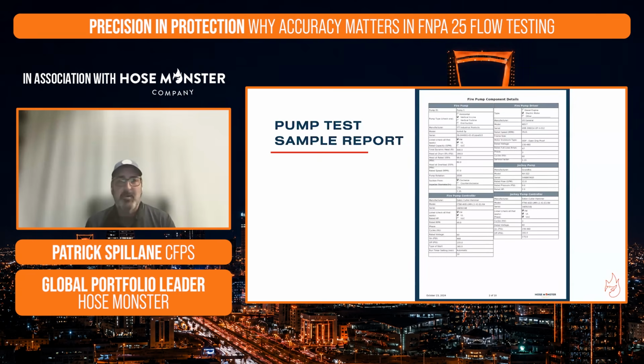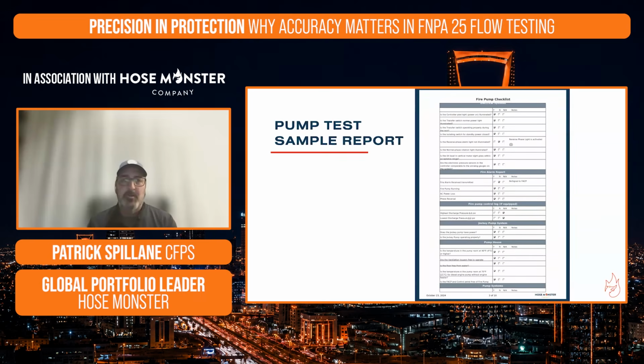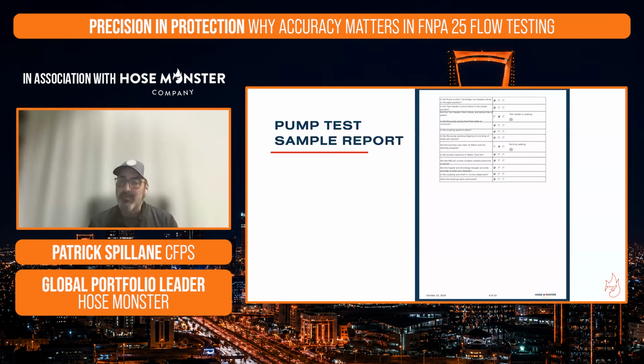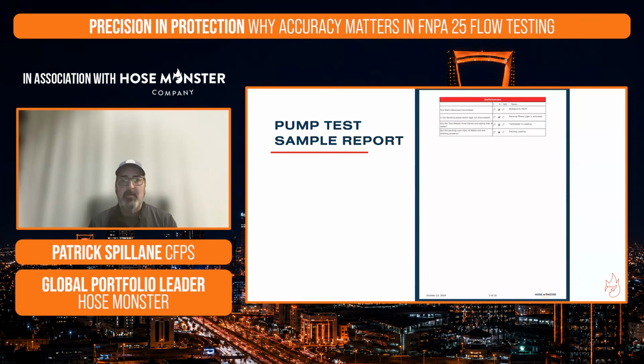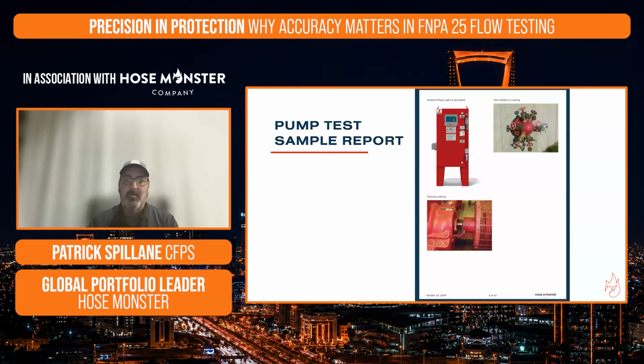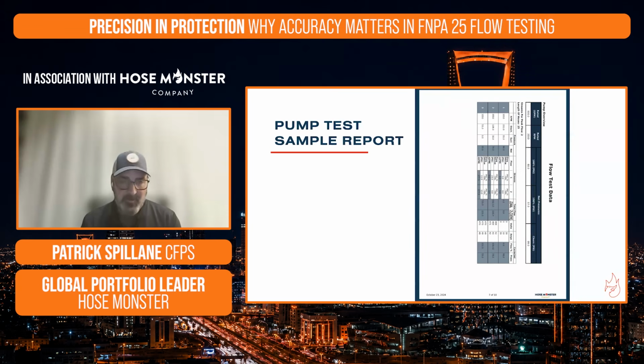all the data that we can enter about that fire pump, our placard information, every component that's in that fire pump room. It's going to take us through an NFPA style checklist, yes, no, NA. We can document any notes. We can take photos of any deficiencies as well. And those deficiencies will be noted on a deficiency report page here. But then the photos will also show up on our photo page, where we can match the deficiencies to the photos as well, so we can see how that test went.